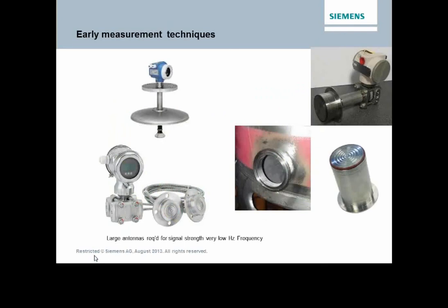So we get specifically to radar, and we talk about early measurement techniques. Quite often what you had was a tank spud that would be welded to the side of a tank, and then a process diaphragm seal. In this case, we're looking at a tri-clamp style that would fit into that spud, and we would be sealing at the end of the spud. This would actually work well in tanks that had material buildup. You could define the extension length into that process and basically clamp the device here, which works fine, and it's still used a lot today. However, if you have a problem with the device, you can't just remove it. The tank itself has to be completely emptied.